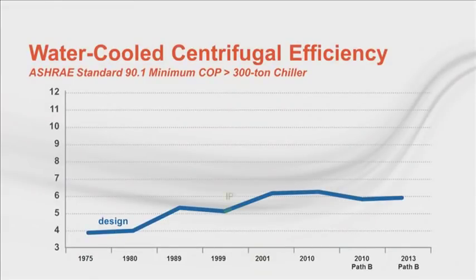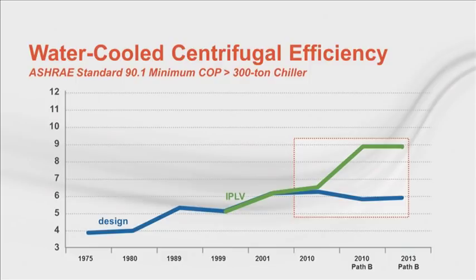Here's a historic graphic that shows the increase in ASHRAE 90.1 minimum chiller efficiency in terms of coefficient of performance, or COP. The two lines represent full load COP at AHRI standard conditions and the integrated part load value, or IPLV. Now, as a reminder, IPLV was first required by 90.1 1999, so until that time it is not plotted. You probably already noticed the split in 2010, introducing Path A and Path B. We see that minimum chiller full load efficiency flattens out between 2010 and 2013.